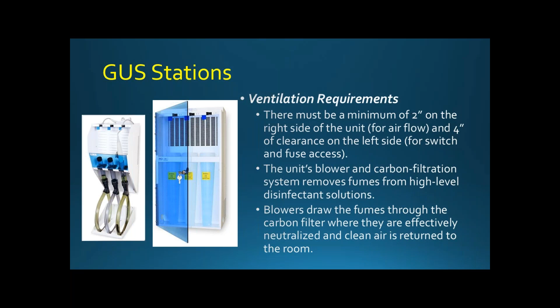You're not supposed to be taking that high-level disinfectant outside of that station prior to it having its first rinse. And I will say that a lot of times when I've done audits, that's where I find the challenge: they're taking the probe from the high-level disinfectant in the GUS station to a sink to do a rinse, when really they need to be doing that first rinse in the GUS station. It needs to have appropriate clearance, because a lot of times GUS stations aren't in a negative pressure room, so this is basically creating that environment for you to meet the requirements of high-level disinfection, and making sure that you are having protection for your staff against the fumes and everything from the disinfectants.